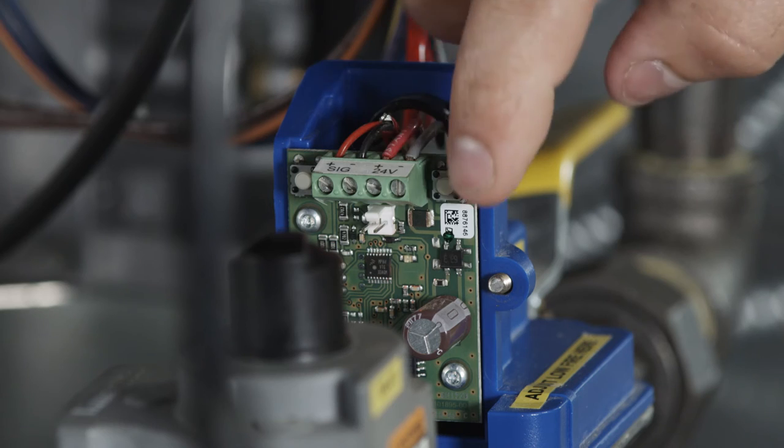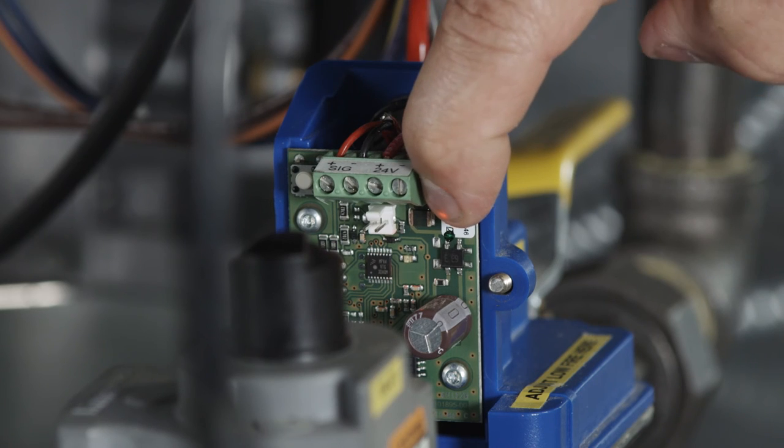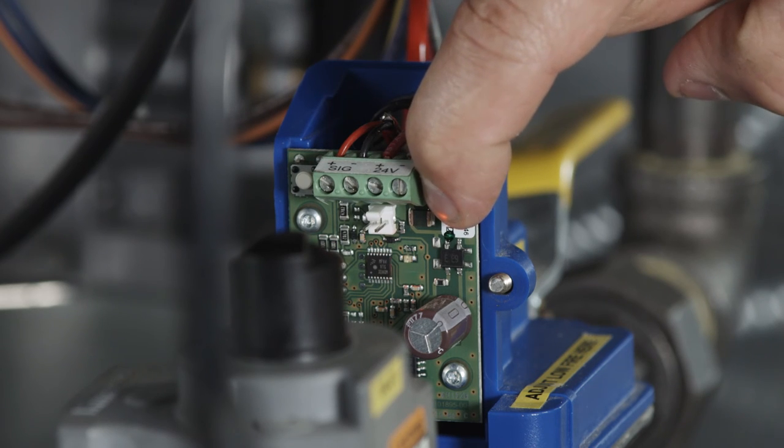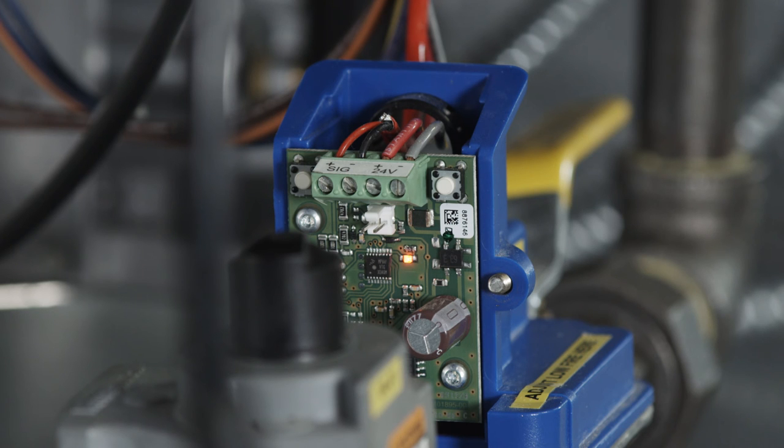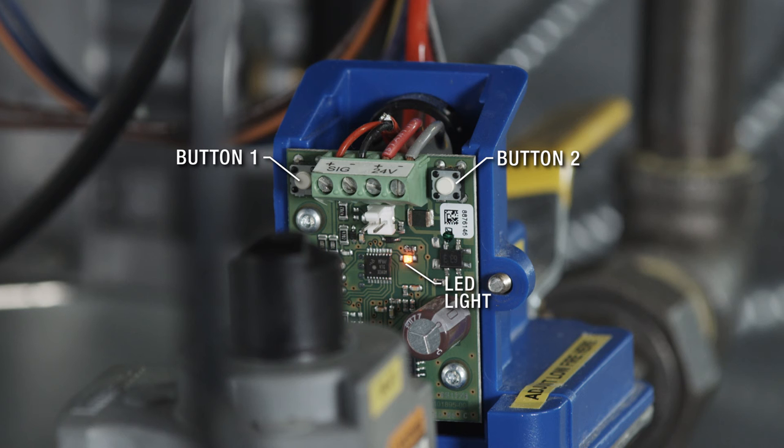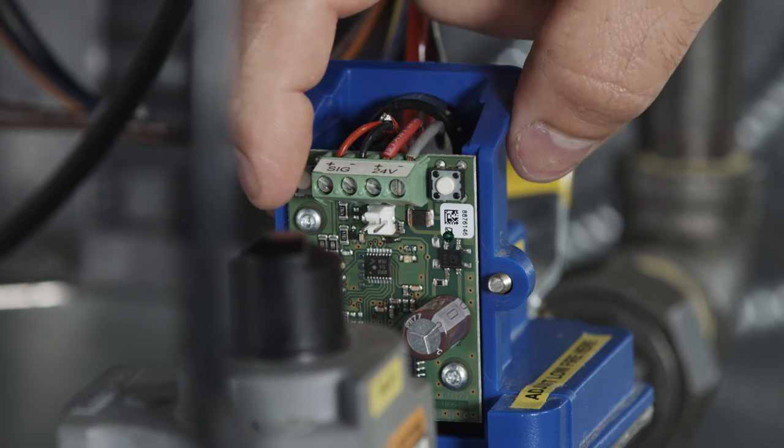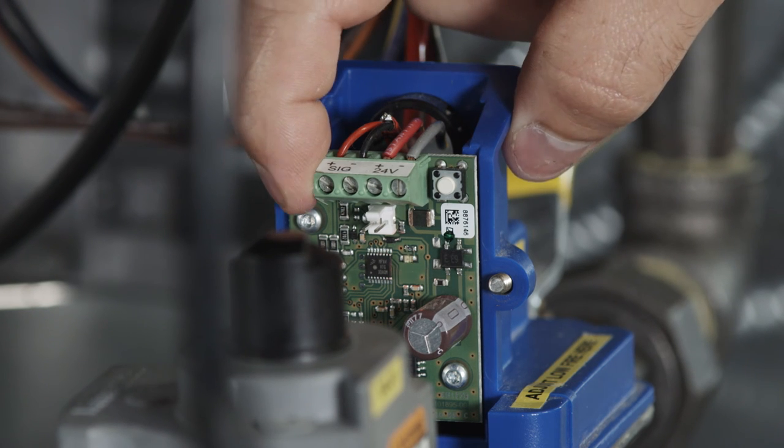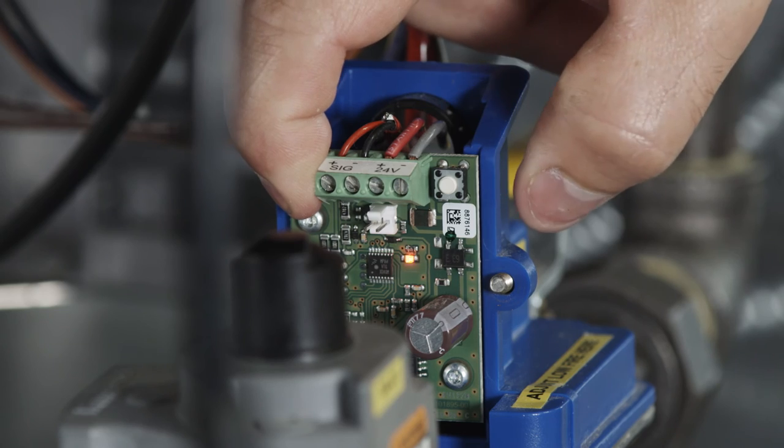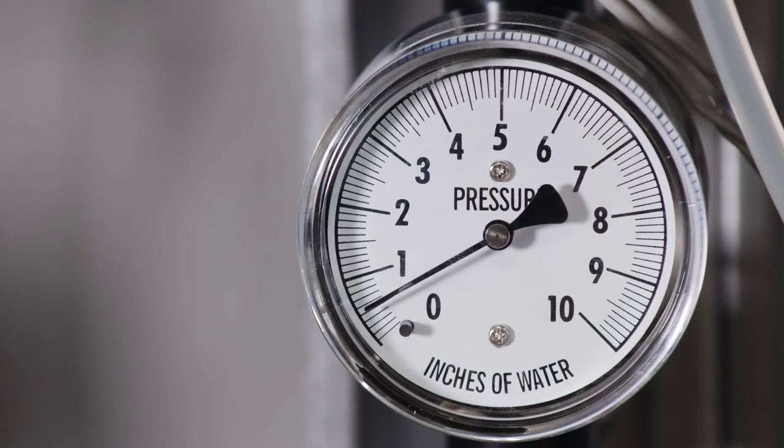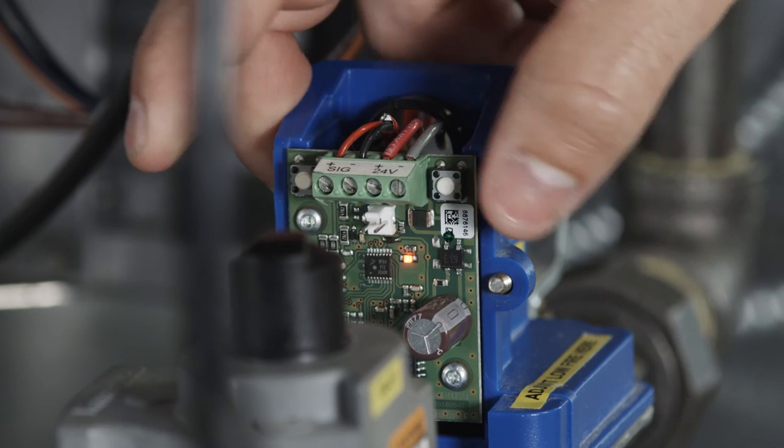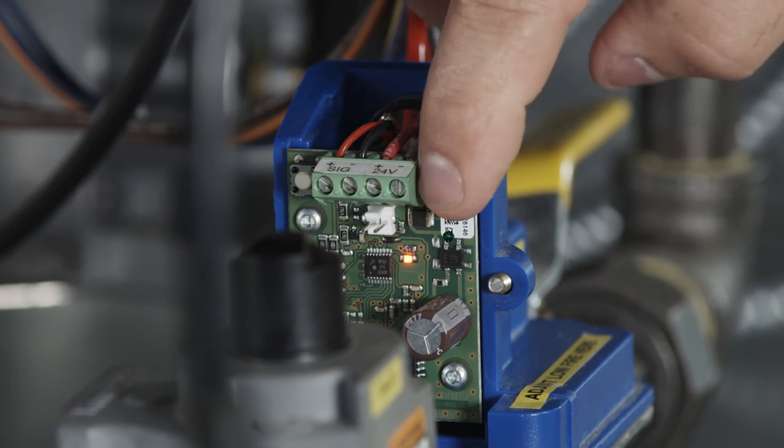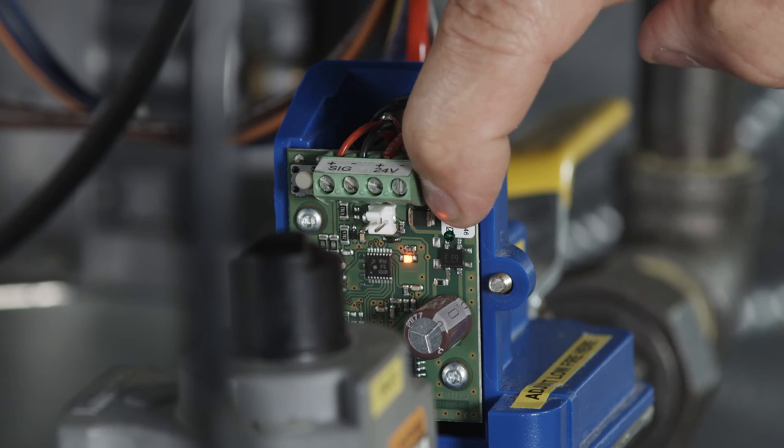Next, press and hold button 2 until the LED light blinks red, then release. The valve is now in low fire setting mode. Buttons 1 and 2 are now used to set desired low fire settings. Button 1 increases pressure. Button 2 decreases pressure.